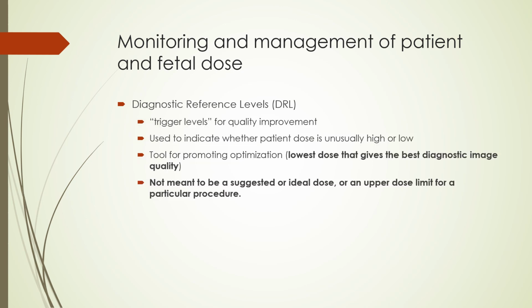The Diagnostic Reference Level, or DRL, is intended to identify situations where the level of patient dose or administered activity is unusually high. The DRL is usually the absorbed dose in air or in a tissue equivalent material at the surface of a simple standard phantom or representative patient. If the diagnostic reference level is consistently exceeded, there should be a local review of procedures and equipment to determine whether the protocol has been adequately optimized.